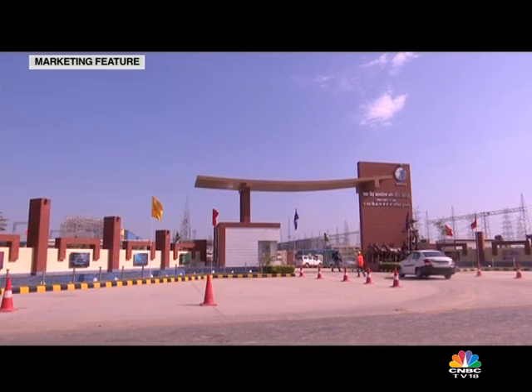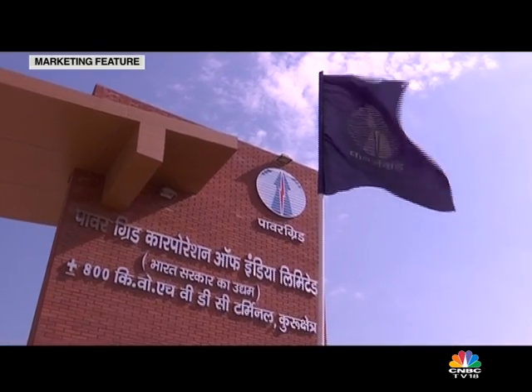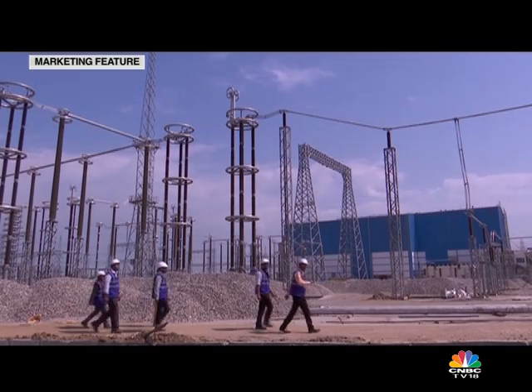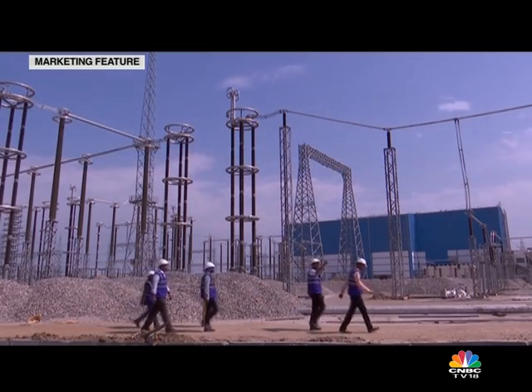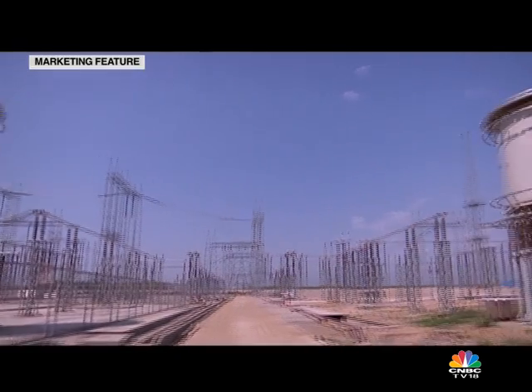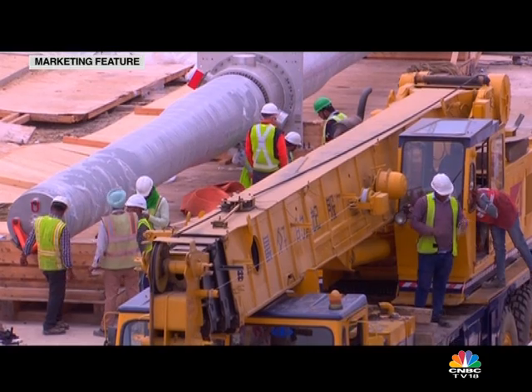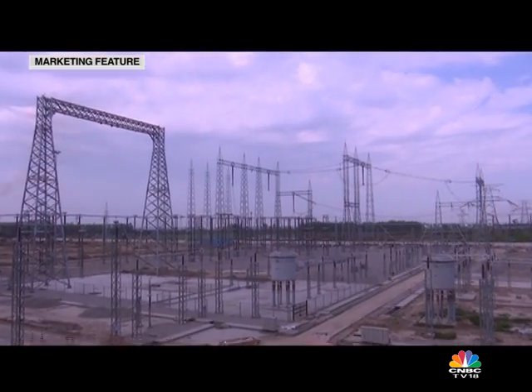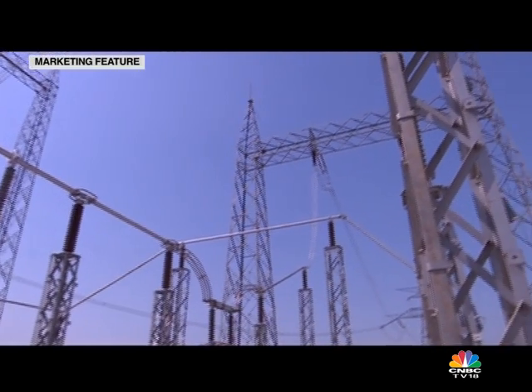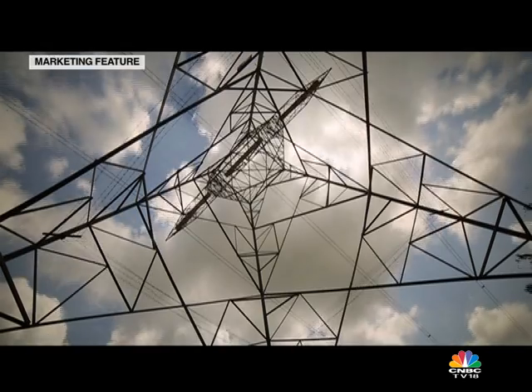Champa Kurukshetra is mainly built for evacuation of power from Chhattisgarh to Kurukshetra in the northern belt. This is a 1300-kilometer link with a capacity of 6,000 megawatts, at a voltage rating of 800 kV plus minus. As on date, we have 12 HVDC systems in the country, out of which 10 belong to us. This is the biggest HVDC system in the world owned by one utility.